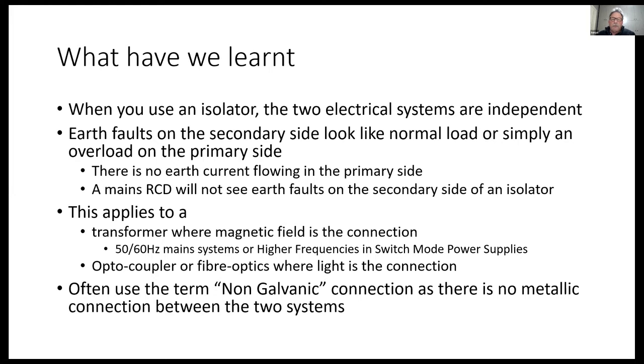So if you get faults on the secondary side, all they'll do is look like normal load or an overload on the primary. You will not get any earth current flowing back into the primary side.